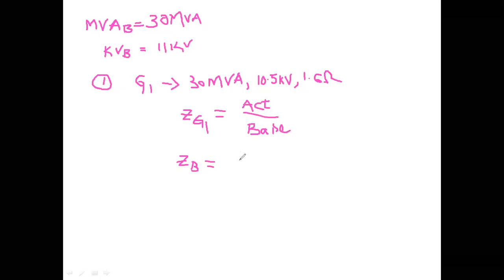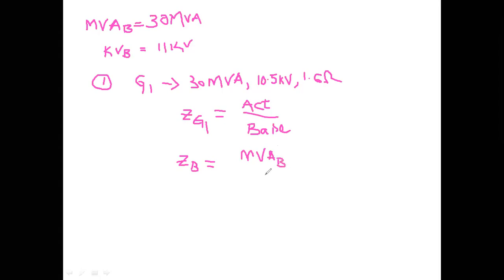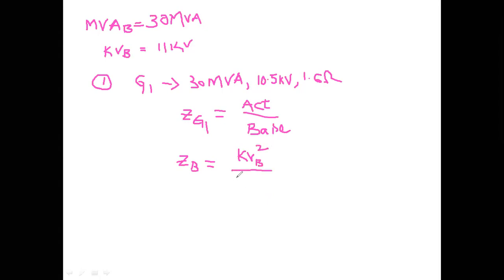Z_base can be obtained from the formula: Z_base = KV_base² / MVA_base. This is the formula used to determine the base value of impedance for any component when the actual value is given. However, if a per-unit value had been given instead of an actual ohm value, you would use the conversion formula: Z_pu_new = Z_pu_old × (KV_base_old / KV_base_new)² × (MVA_base_new / MVA_base_old).